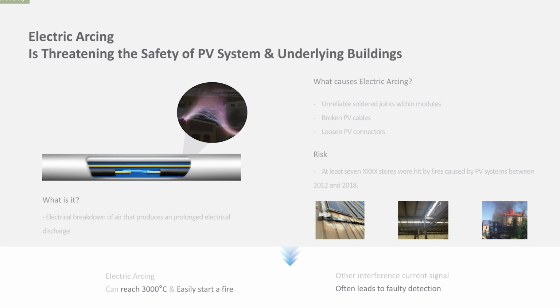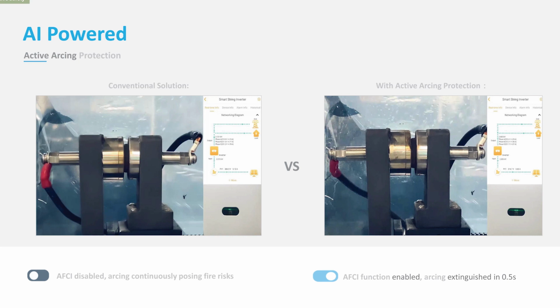The risk is that these things actually arc at something like 3,000 degrees. And you can't stop that arc, okay? You can't put anything to stop that arc unless you have a circuit which can interrupt the connection between positive and negative, okay? So there's an example of what the arcing looks like. It's continuously arcing, all right? It's without AFCI. And on the other screen, you can see it stops. Okay, let's play this one. So you see it immediately stops, okay?